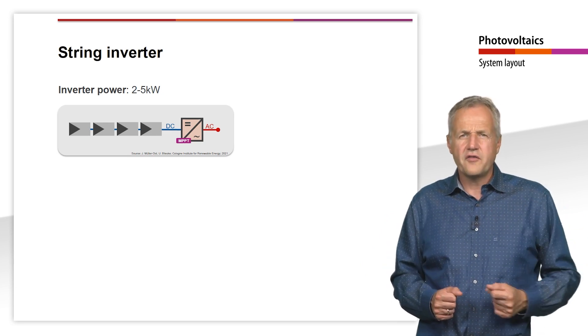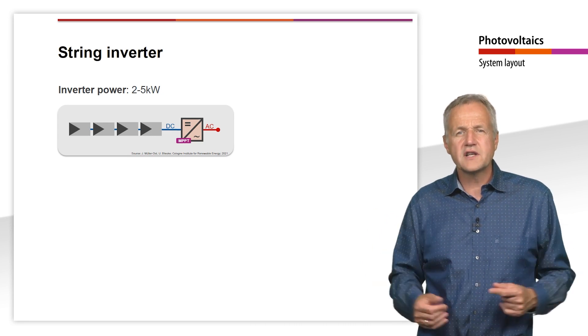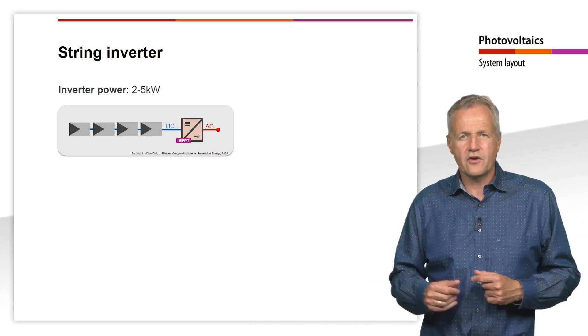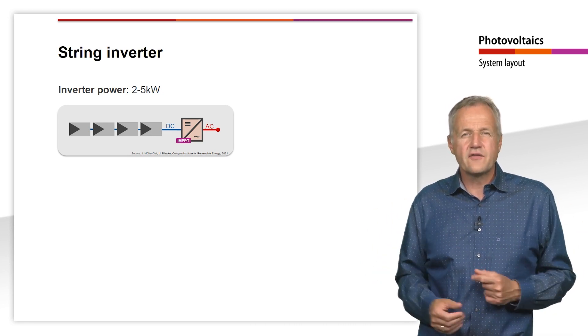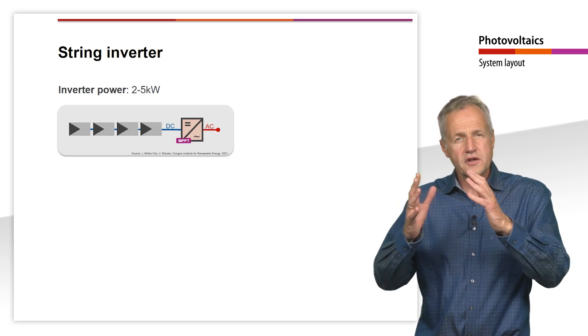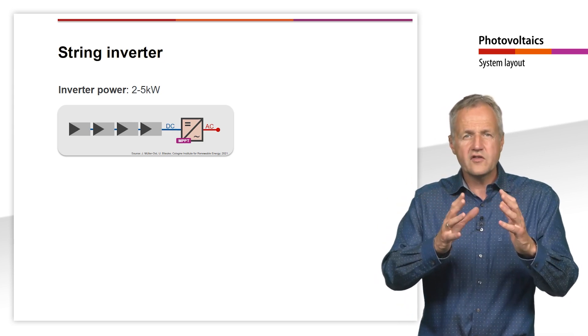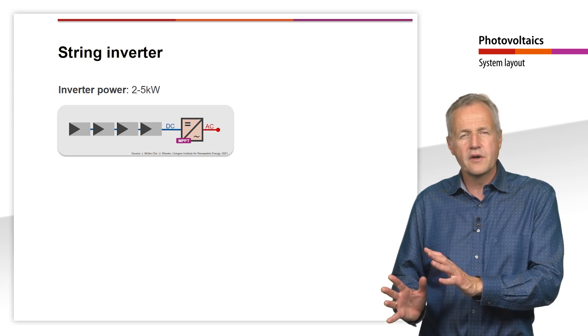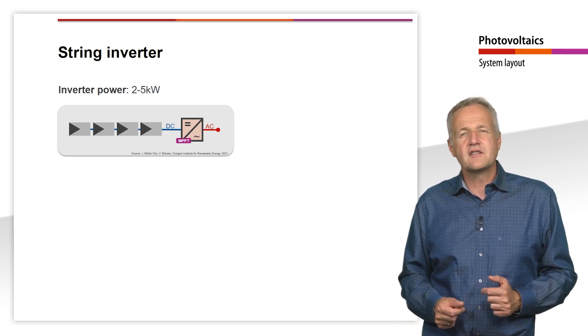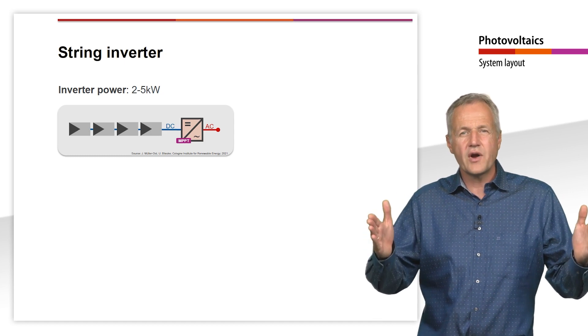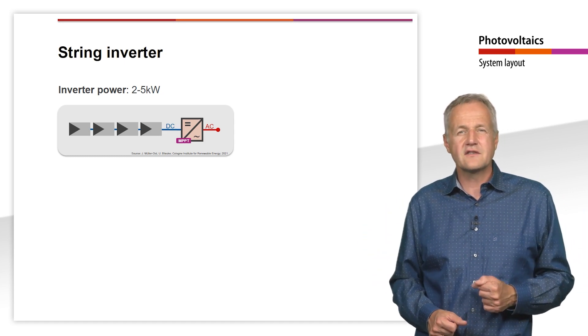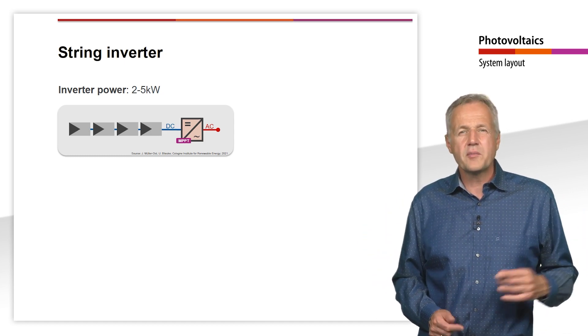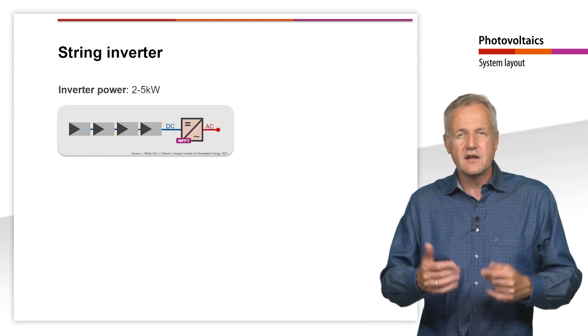The vast majority of systems on residential buildings are equipped with such a string inverter. To protect the inverter from the weather, it is usually not directly installed next to the modules but in the basement of the house or technical room. The reason for connecting the modules in series and not in parallel is the same as for connecting the cells in the module. The ohmic power losses increase quadratically with the current.